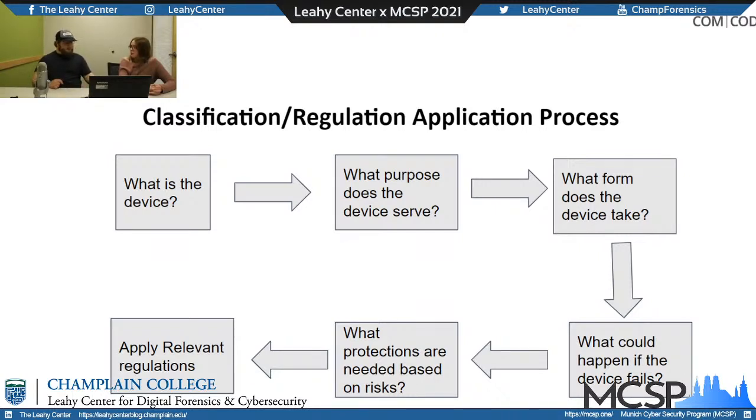Because the post-market device system that the FDA has, their most recent one, was published in 2014, which is binding. You have to follow it. But they've released a guiding document in 2018 that's under review that changes the whole system of how they're going to secure a device, but it's only recommended. So it's like, you should do this, but if you don't, we're not going to say good job, but we're going to say, okay, you can still get it. Okay, so it's a lot of third parties involved.